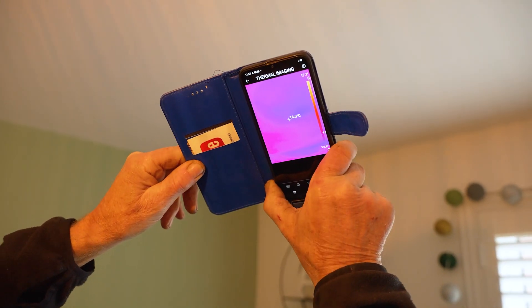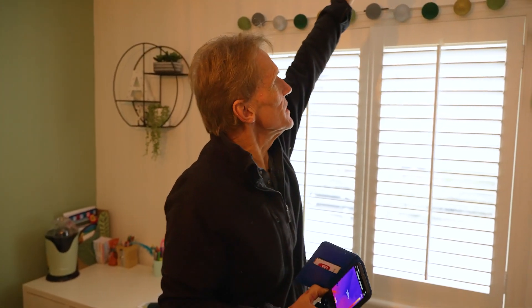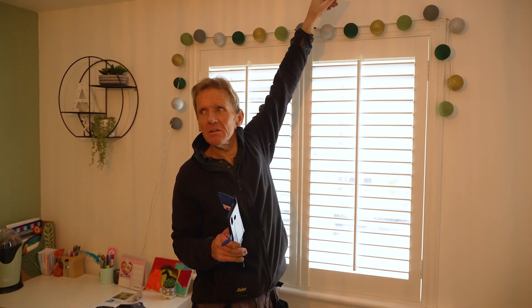All the way along the top here there's a bit of cold bridging, a bit in the corner. So that's the gable end, and the room upstairs starts about there. That bit is a flat ceiling where they would have put insulation, and I think what's happening is they haven't pushed it down in the ends. They want ventilation, but the insulation in the wall - whatever that is, maybe rock wool or something - it's clearly not pushed right up to the top. It's always in the details. People do a great job on all those bits as they're building the wall, but just at that top bit the brickies are finished and the carpenters come along - whose job is it?